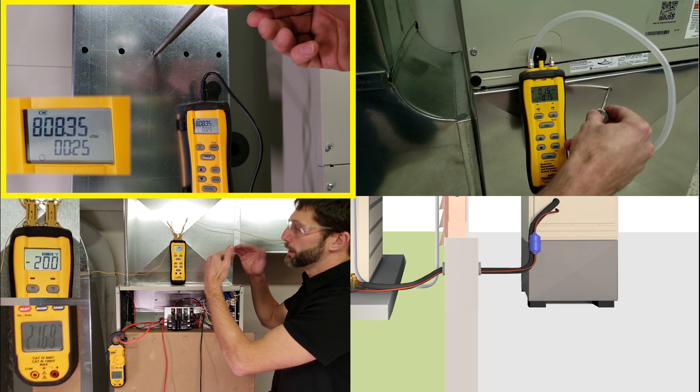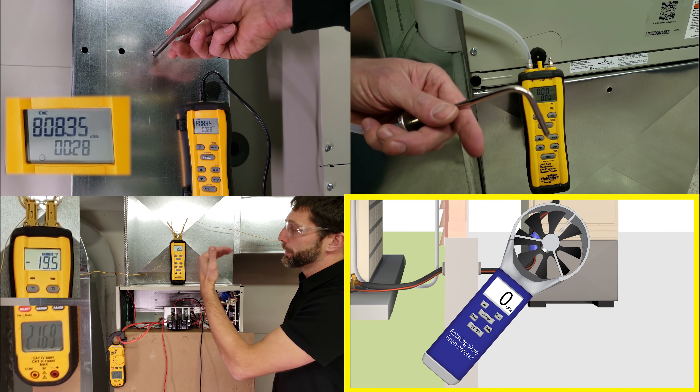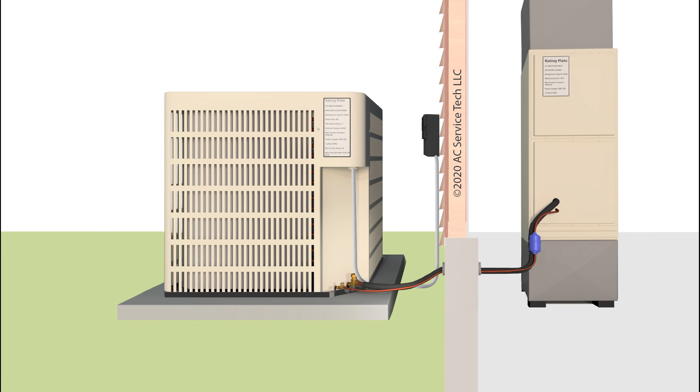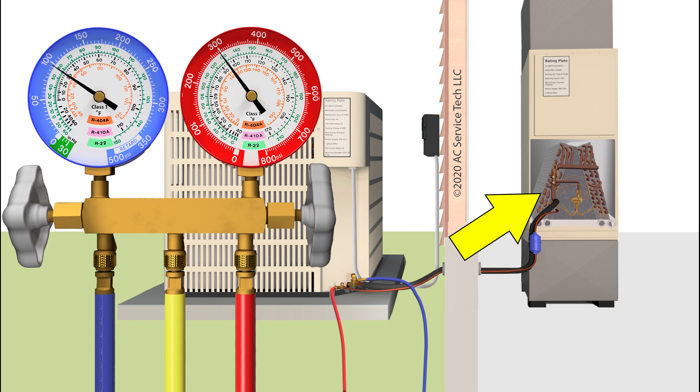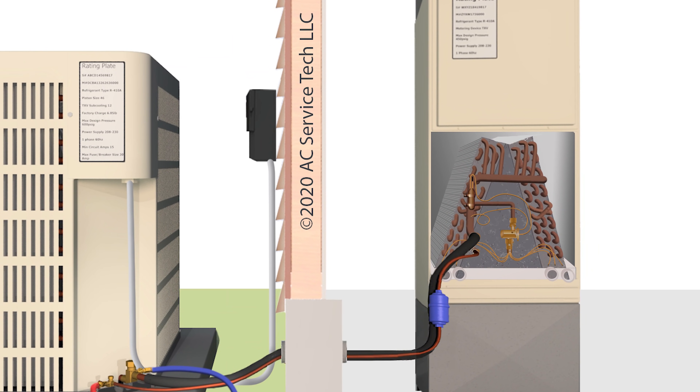You can also check it with a rotating vane anemometer or with a flow capture hood. Right there you should be able to determine if you have a low airflow problem. If we were to go ahead and turn the system on when you have a frosted evaporator coil, we're also going to need to know if we have a TXV metering device or a fixed orifice metering device, such as a piston or capillary tube, and you're going to be able to see that at the indoor evaporator coil.